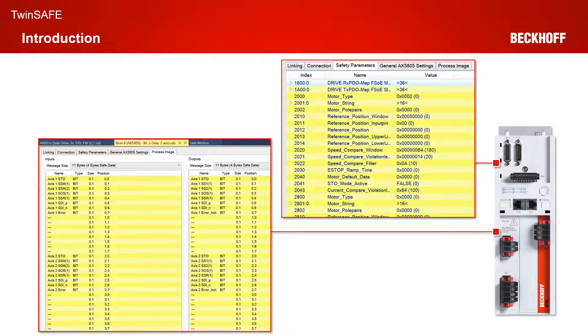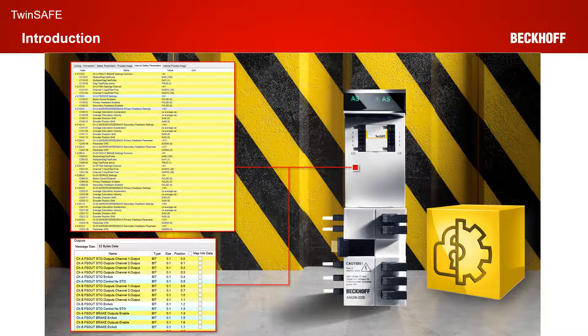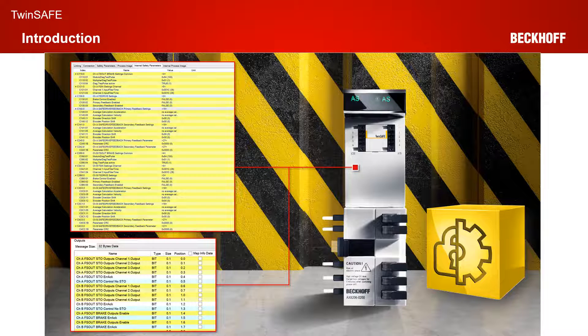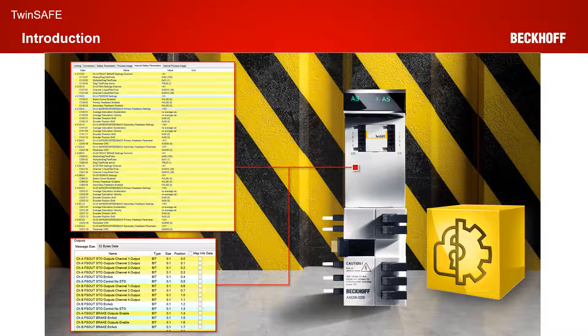However, the safety functions still have to be within the limits of the device's firmware and can only be configured. That's why we took it a step further with the AX8000 and its integrated TwinSafe logic. If you buy an AX8000, there is already a safety project active within the safety option. But the default project only realizes an STO functionality which can be triggered via FSoE or hardwired. In order to realize more complex safety functions like safe limited speed, you can program the integrated logic.